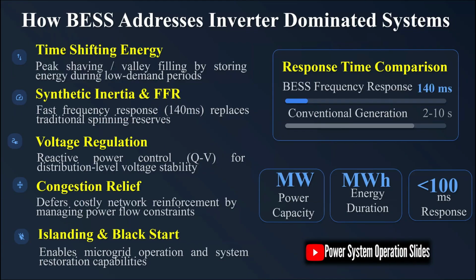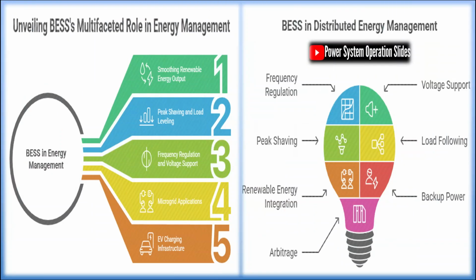More critically, the reduced system inertia inherent in inverter-based resources means that the grid's ability to resist frequency disturbances is diminished. System inertia, provided traditionally by the rotating mass of synchronous generators, acts as a buffer against frequency changes. When this inertia is reduced, the grid becomes more susceptible to frequency excursions and potential instability. BESS addresses these challenges through multiple technical mechanisms.